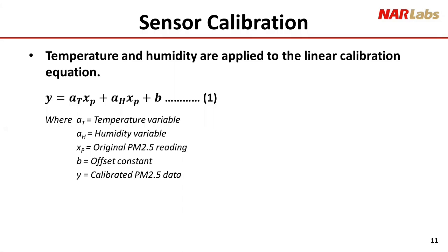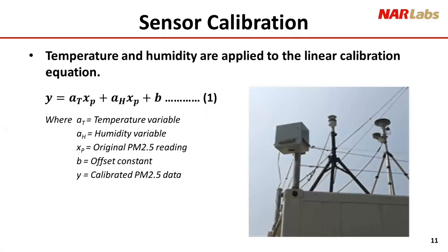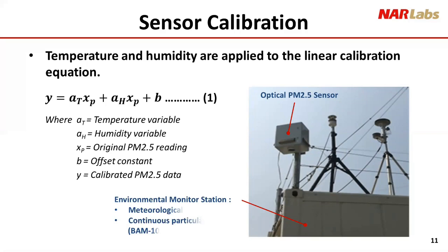To build the linear regression model for the calibration equation, we ran a 45-day field experiment, cooperating with the local Environmental Protection Bureau. We placed the optical PM2.5 sensor close to the environmental monitoring station and collected data at the same time. The station is equipped with a meteorological sensor and a continuous particulate monitor. With those reference data, we can then build a linear regression model for the low-cost PM sensor.